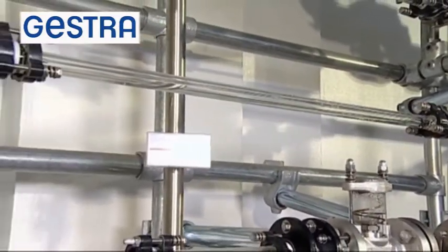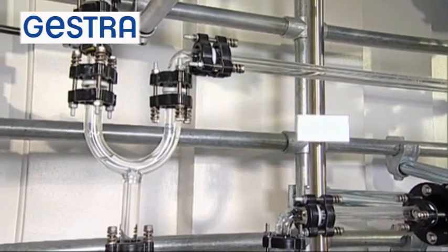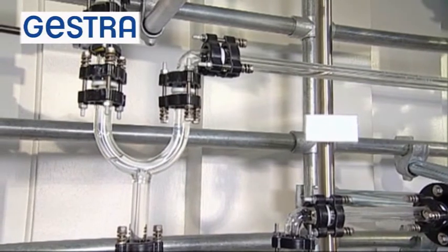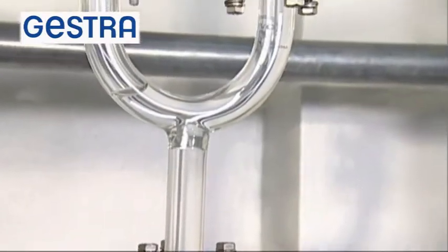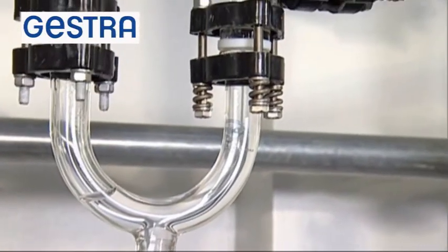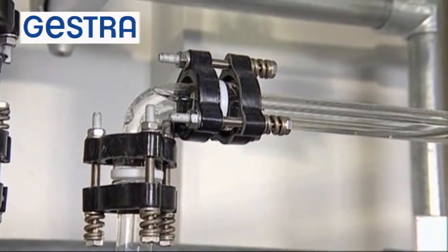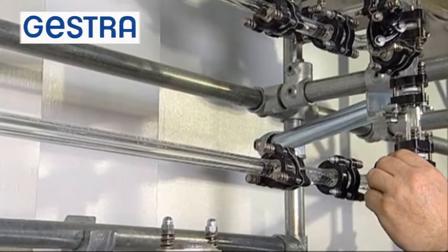This time, however, this part of the horizontal tube is arranged to have a slight drop towards a siphon. Having the siphon downstream ensures that there is always a steam bubble in the horizontal part, and the water flows along the bottom. Through their volume, the steam bubbles at the top of the tube form a buffer space, which minimizes the water hammer at startup and allows the startup process to be initiated faster and with less risk.